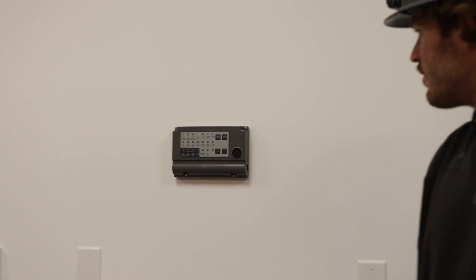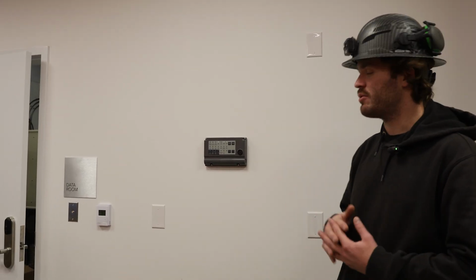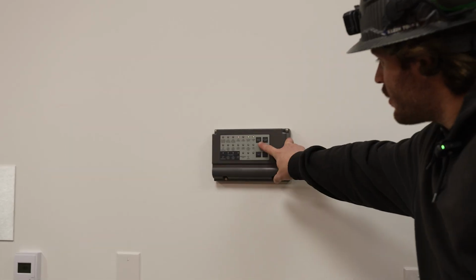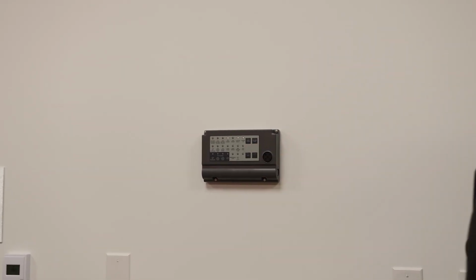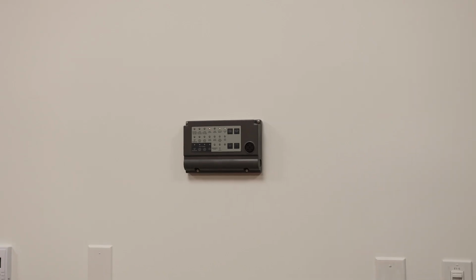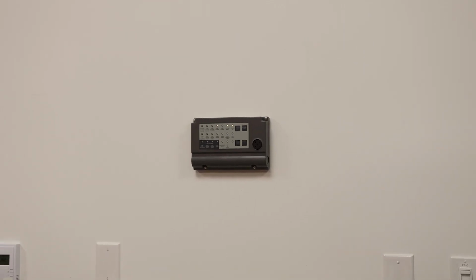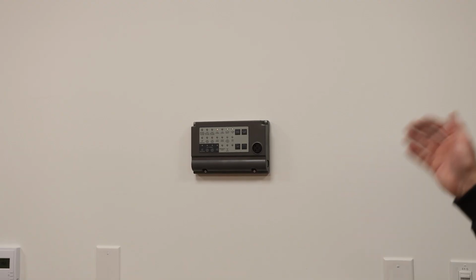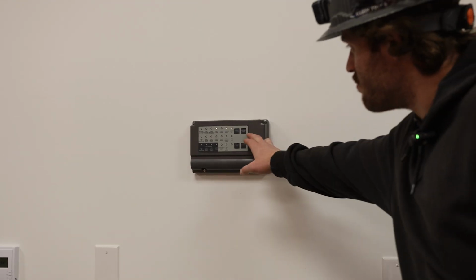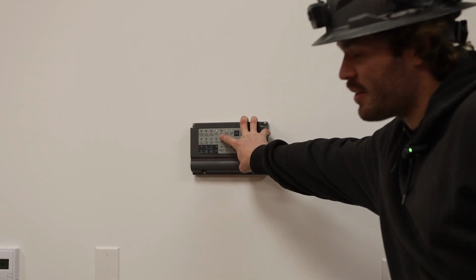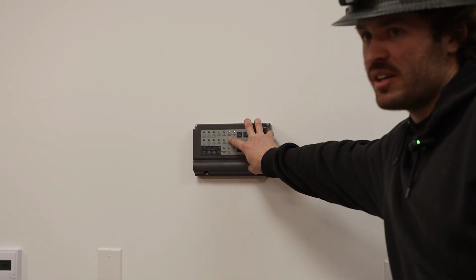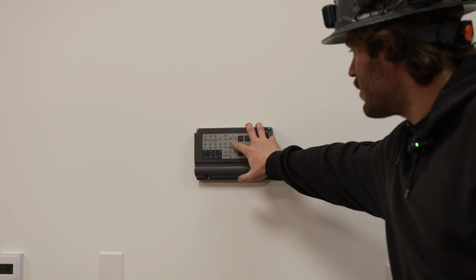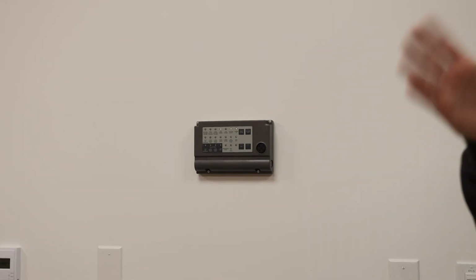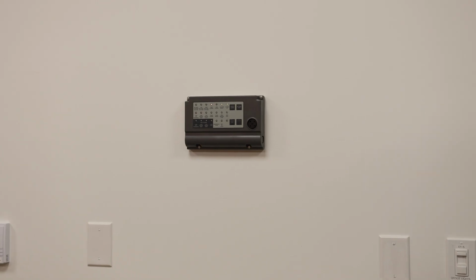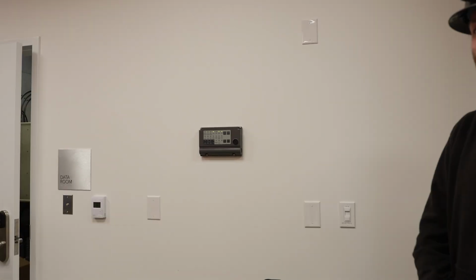To silence it in the event of a nuisance alarm, like say you're at 19% fuel level and it's buzzing, reset alarm will silence the panel until another fault comes into it. Other than that, there's really not much to be done with it. Just ensure that you see the lights on it. These are the normal lights to see: gen power, meaning the breaker is on the generator, system ready, meaning the generator's in automatic, and communication okay. It just relays what the generator is doing. It doesn't have anything to do with their transfer switch. Pretty simple. It's just going to sit there and beep.